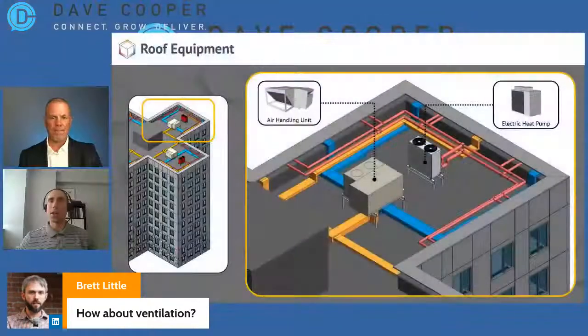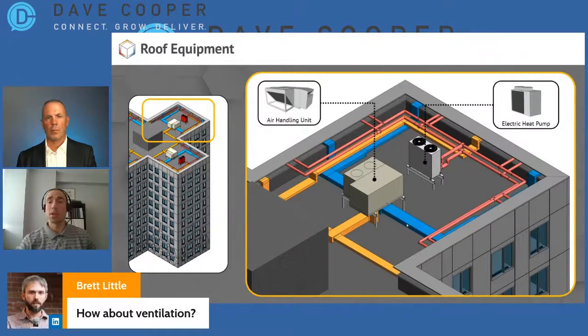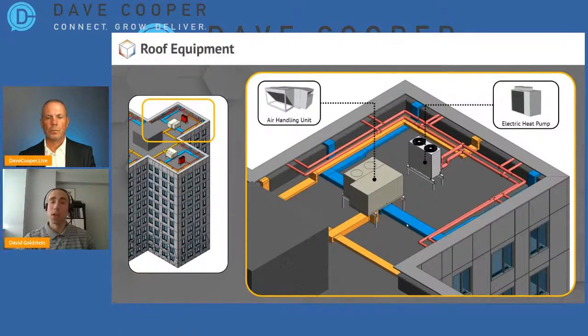How about ventilation? Yep, so ventilation is a key part of this. Basically, we're installing packaged rooftop units that will be fully conditioning ventilation air. So we're talking about tempering the air, also filtering the air and dehumidifying the air, having this fully conditioned ventilation air that's going to be distributed throughout the shell and to each of the apartments. That unit is also taking exhaust from the kitchens and the bathrooms, running it through energy recovery before exhausting it out of the unit. So yes, ventilation is a part of it, it's a hugely important part, and that's one of the big benefits, as you were mentioning Dave, the poor indoor air quality in so many of these existing buildings and all the health issues that result from that. We can really take a big bite out of that, because we're going to be providing this nice 24/7 ventilation air to all the apartments.